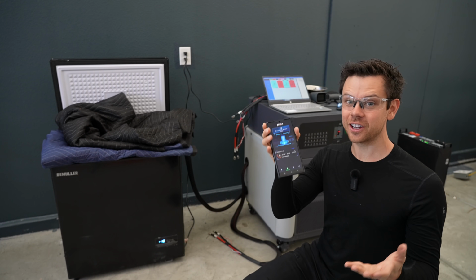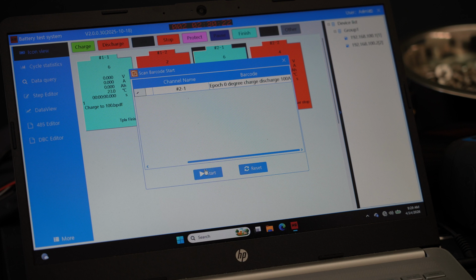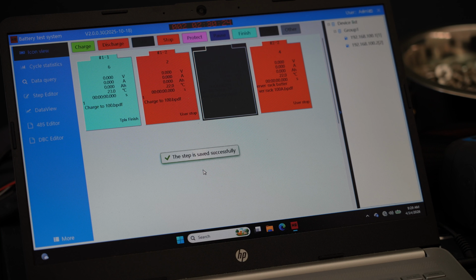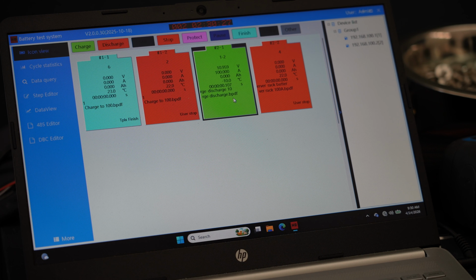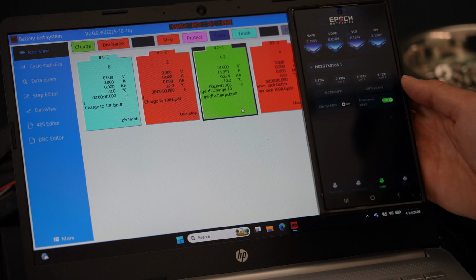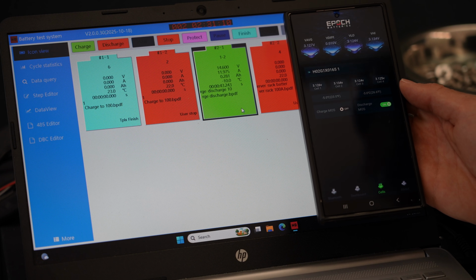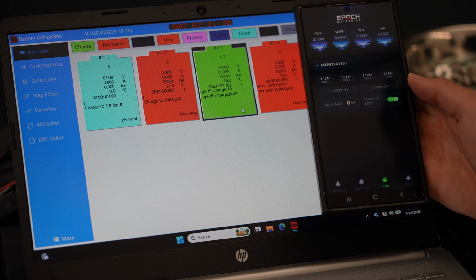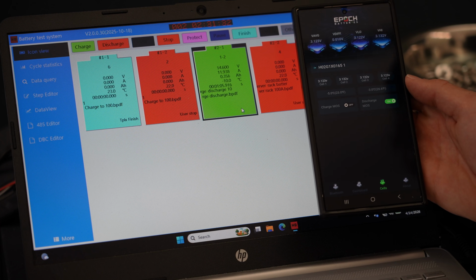So let's try charging it with 100 amps. Here we go. And the test has now started. And it's charging, look at that. So it drew 100 amps for a few seconds and then it dropped down to 12 amps. This is because it's using the internal heaters to warm up the cells.